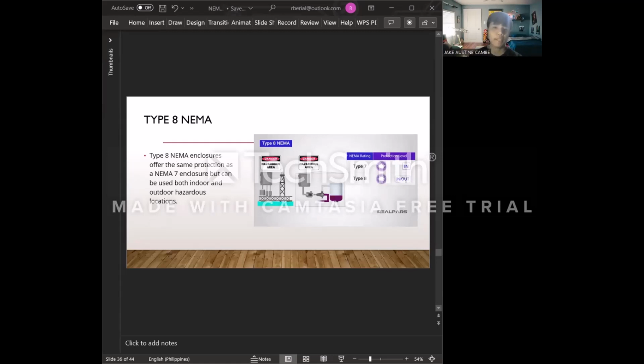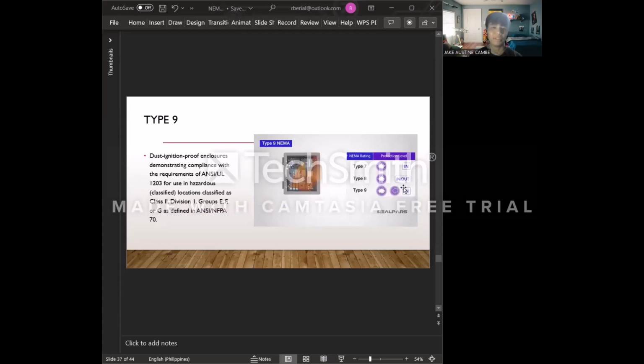So type 8 NEMA enclosures offer the same protection as NEMA 7 enclosures, but type 8 NEMA enclosures can be used indoor or outdoor in hazardous locations.